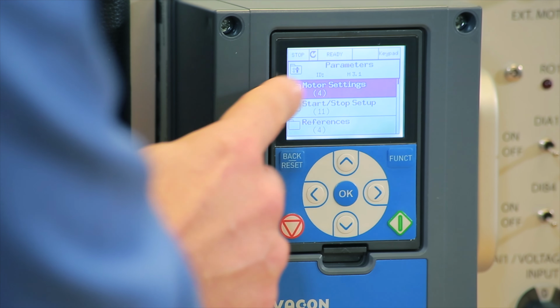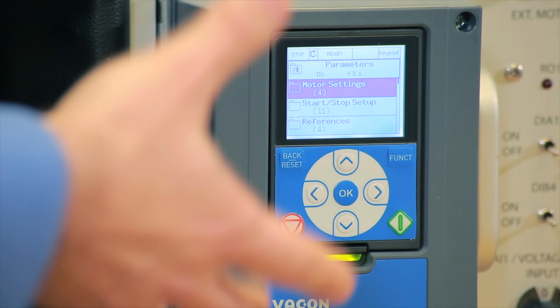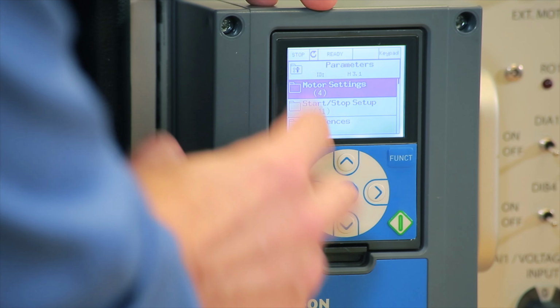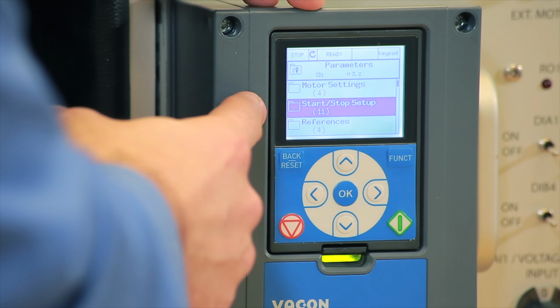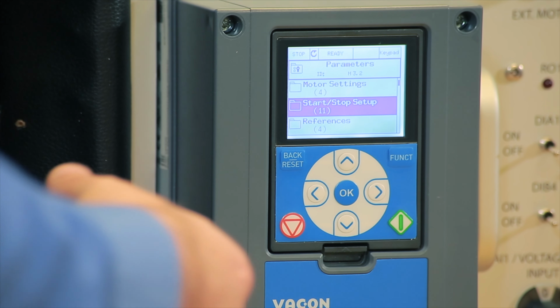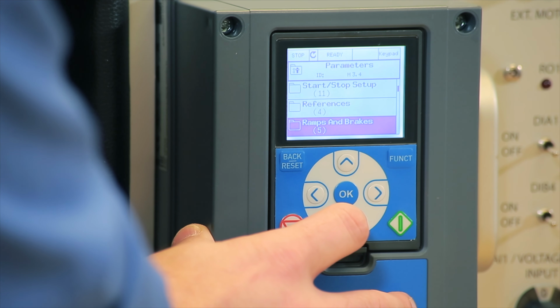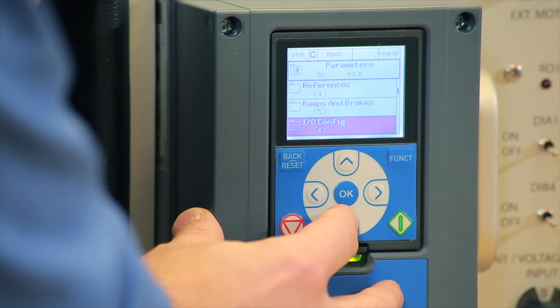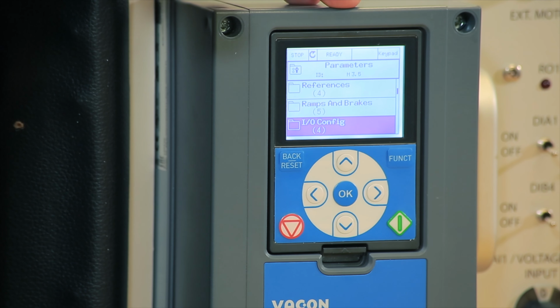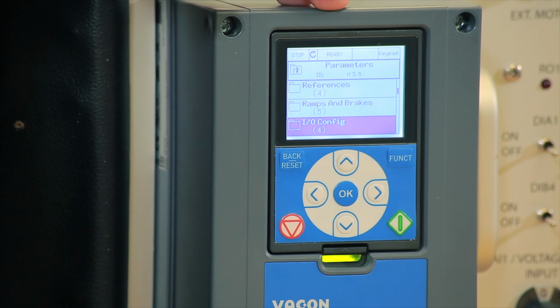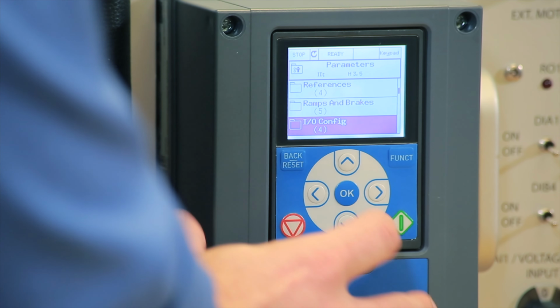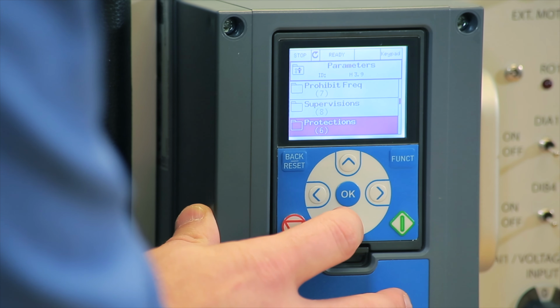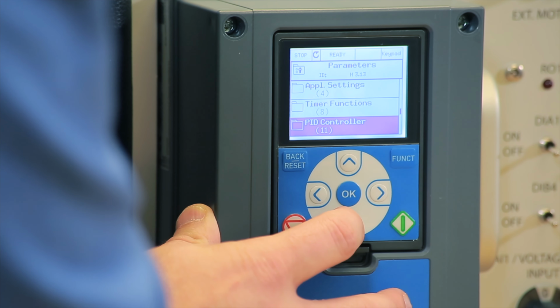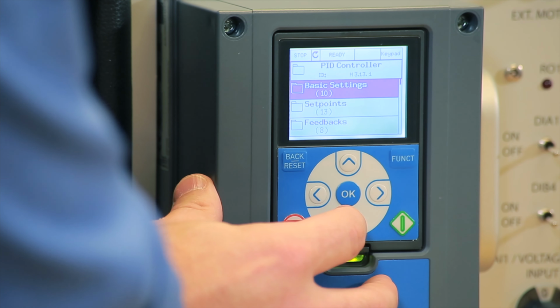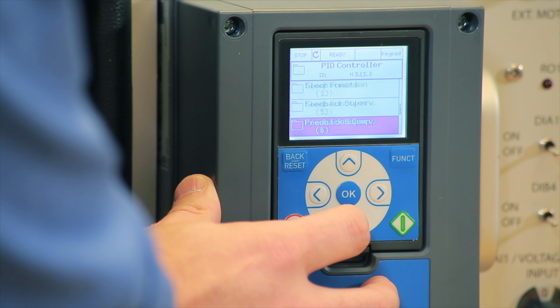We're going to click OK, and then as I'm scrolling down to the PID controller that we want to program, you will see everything along the way: motor settings for full load amps, start and stop if you want a different ramp to stop or coast to stop, speed references, ramps if you want dual ramps, you could go here, input-output configuration. One thing I wanted to quickly mention about input-output configuration is that we can assign different functions to digital inputs, so we can reduce the amount of wiring for digital inputs, which is great. Going down, we're going to go to PID controller.